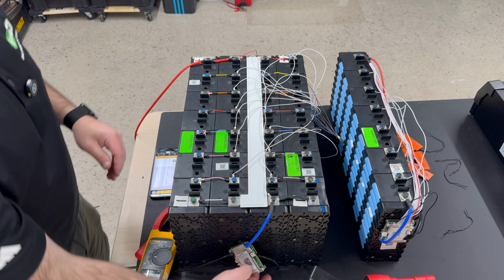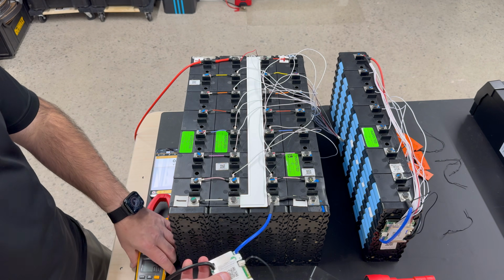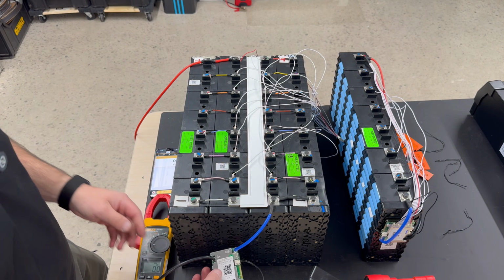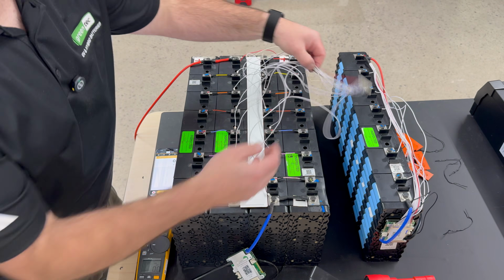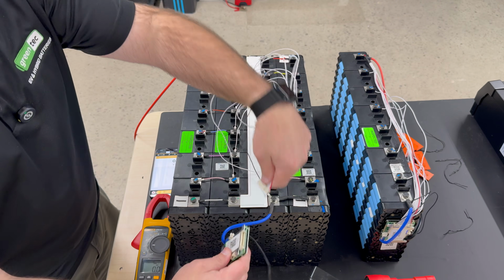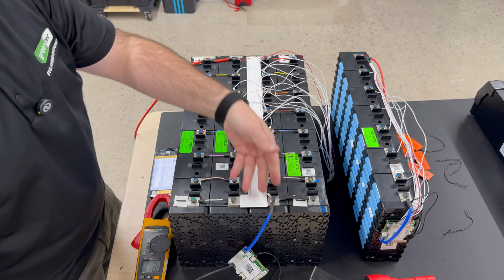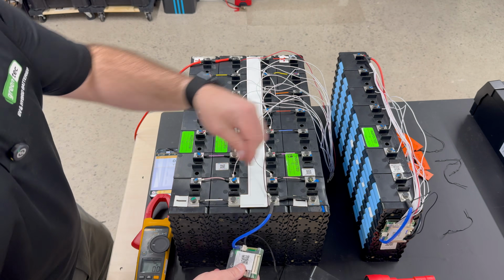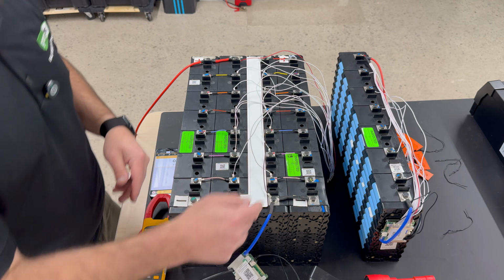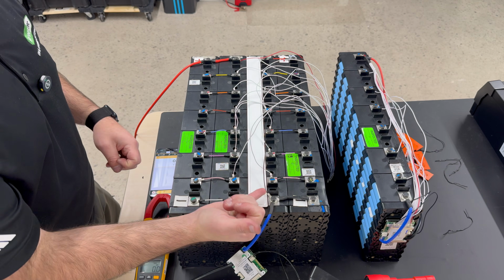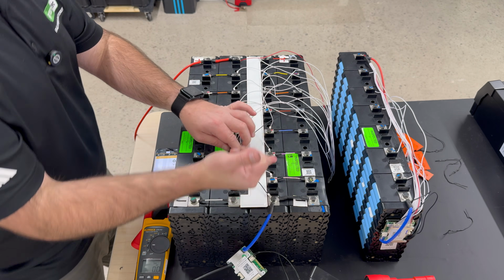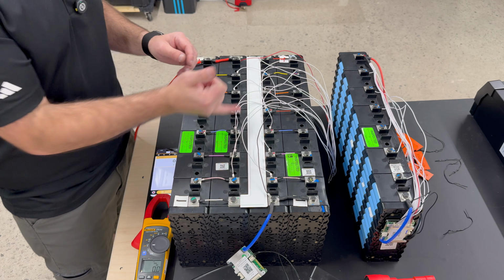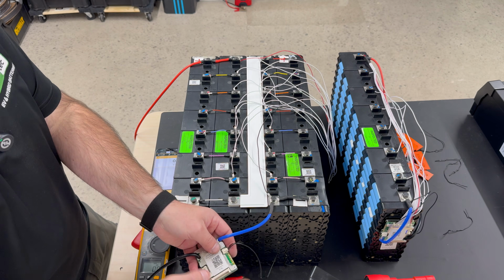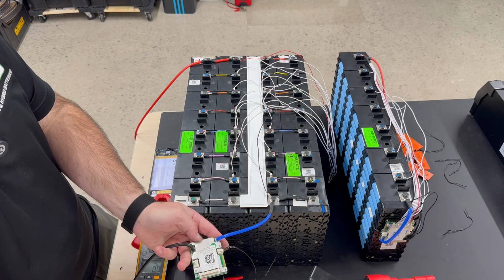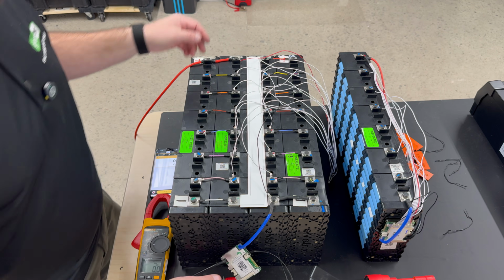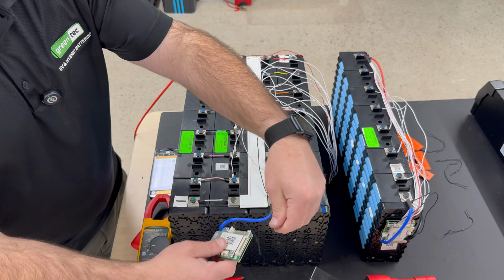So now, according to this BMS's specific instructions, it says not to plug this in directly here. It actually says to disconnect all the wires, then plug it in, and then go ahead and reconnect them, starting with B0 or the black wire, then connecting 1, 2, 3, 4 all the way along, one at a time while it's connected. This increases the voltage slowly so that it doesn't pop and fry out.